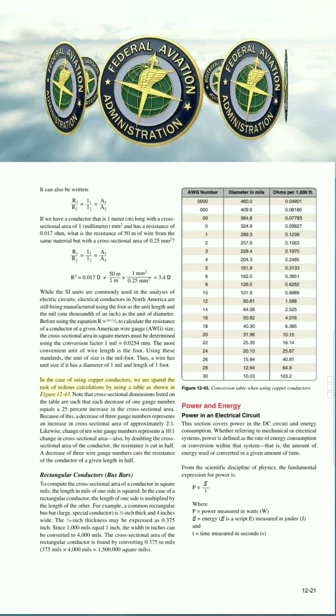While SI units are commonly used in the analysis of electric circuits, electrical conductors in North America are still being manufactured using the foot as the unit length and the mil, 1/1000th of an inch, as the unit of diameter. Before using the equation R equals ρ times L/A to calculate the resistance of a conductor of a given American wire gauge size, the cross-sectional area in square meters must be determined using the conversion factor 1 mil equals 0.0254 millimeters. The most convenient unit of wire length is the foot. Using these standards, the unit of size is the mil foot. Thus, a wire has unit size if it has a diameter of 1 mil and length of 1 foot.